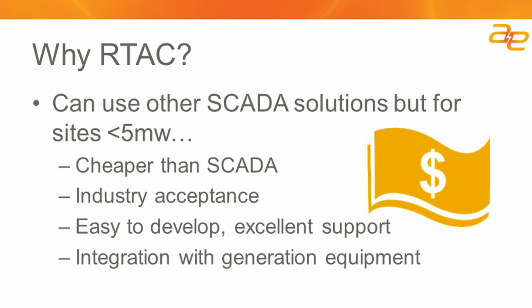So just a couple more points on the case for why to use an RTAC. Some of the monitoring systems have some ability to do controls built into them, but the RTAC itself already knows how to talk to everything that's going to be in the plant. It already knows how to talk to external devices. It's a lower cost device than many of the options that are provided by the monitoring companies to monitor the site. The RTAC device itself, there's a version of it that's available for less than $1,000. So it's an inexpensive device.